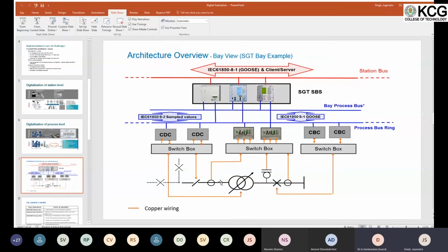There are devices available now. The switch box connects to the merging unit, which is a kind of transducer that converts the analog signal to digital signals, converts the waveform, and sends it to the relays.